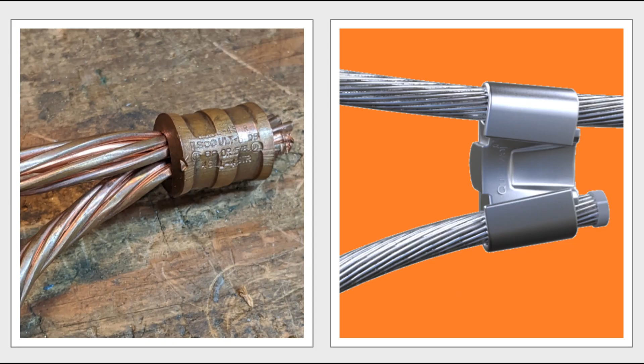The proposed new hardware will facilitate the transfer of phase connection without undoing any primary line connectors. The hardware will have 5 high voltage bushings: 3 terminals for the phase conductor supply and the remaining 2 for the single-phase transformer concerned.